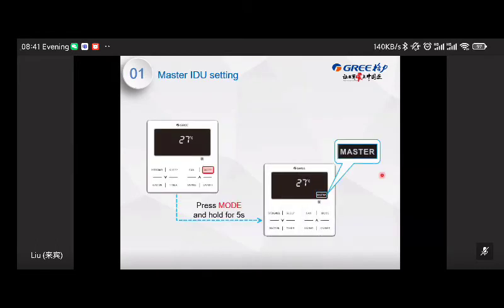Okay. The next one is the master indoor unit setting. For the VRF heat pump, there are many indoor units. Maybe some users choose the cooling. Some users want to choose the heating. So in this case, it may cause mode conflicts, right? For the heat pump, there are just the two copper pipes, gas and liquid pipe, and this unit can just run cooling or heating at one time, right? It cannot do the heat recovery.